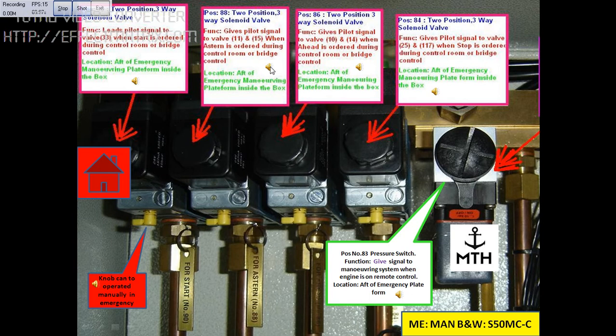This block is position number 88, which is a two position three-way solenoid valve. The function of this valve is to give a pilot signal to valve number 11 and valve number 15 when Astern is ordered either from control room or from bridge control.